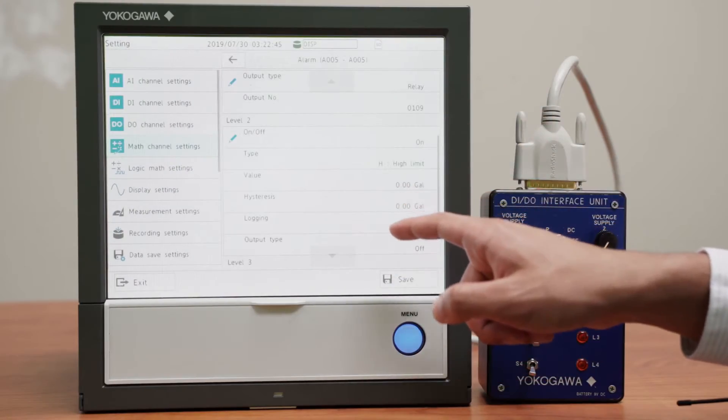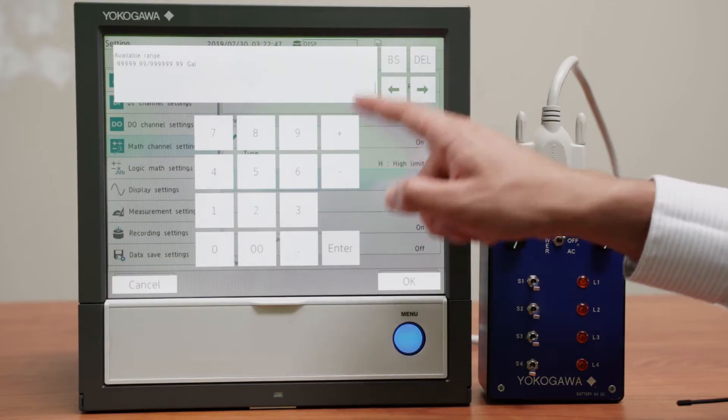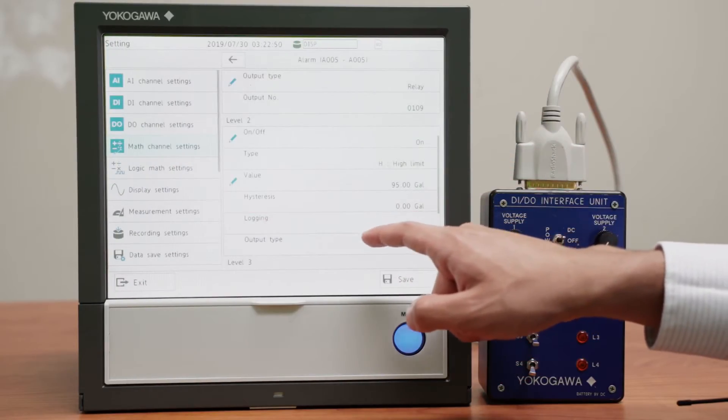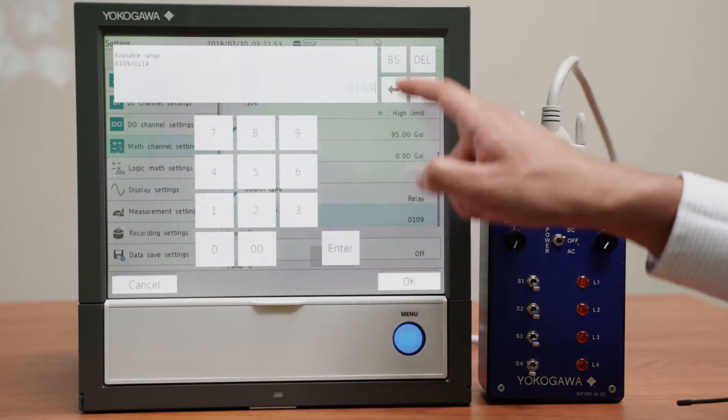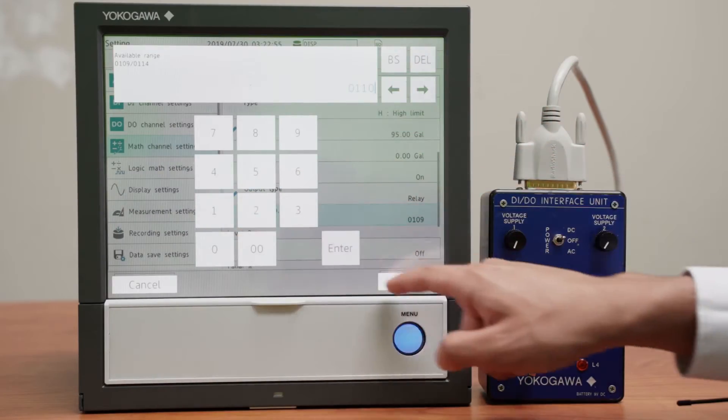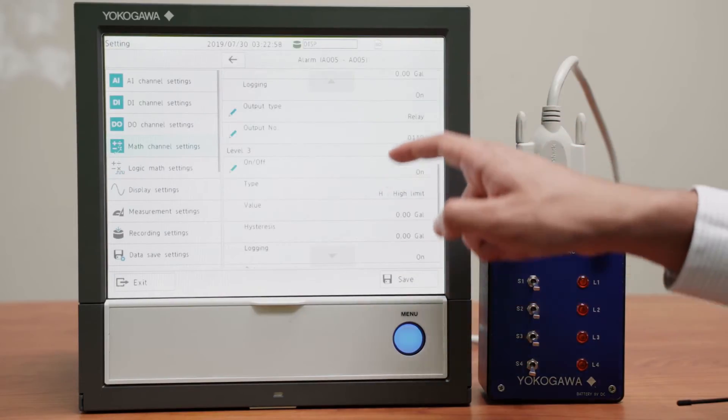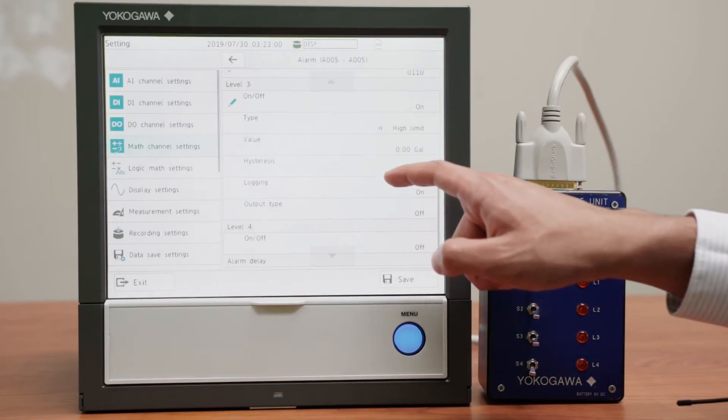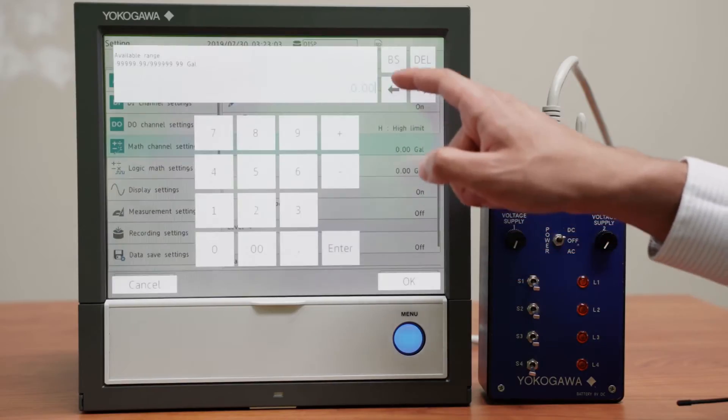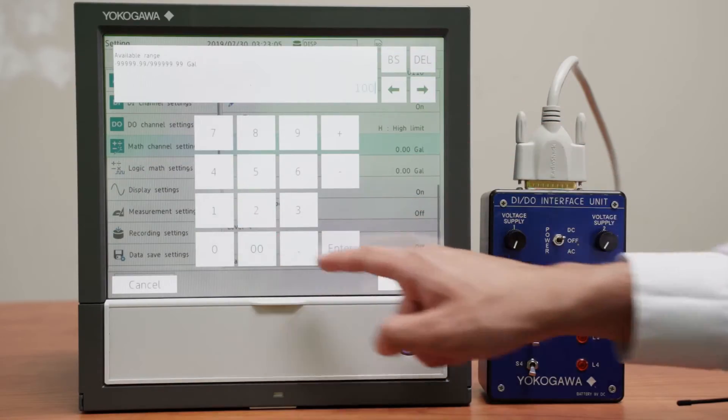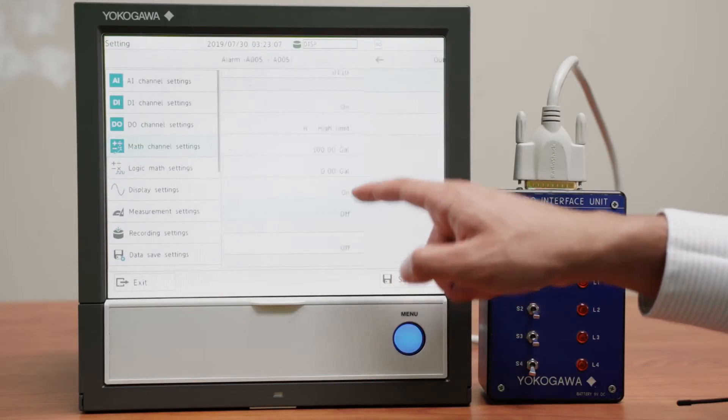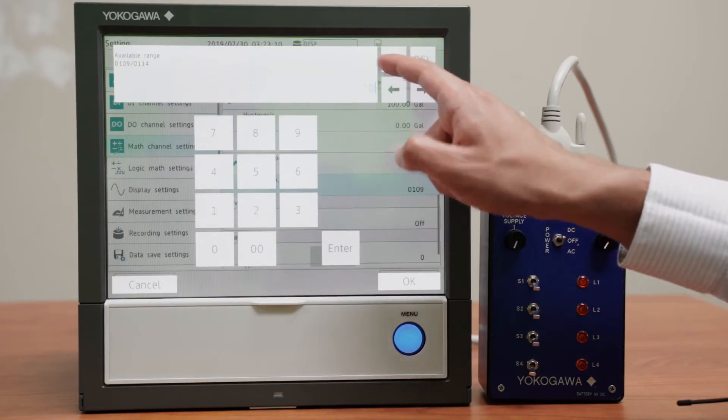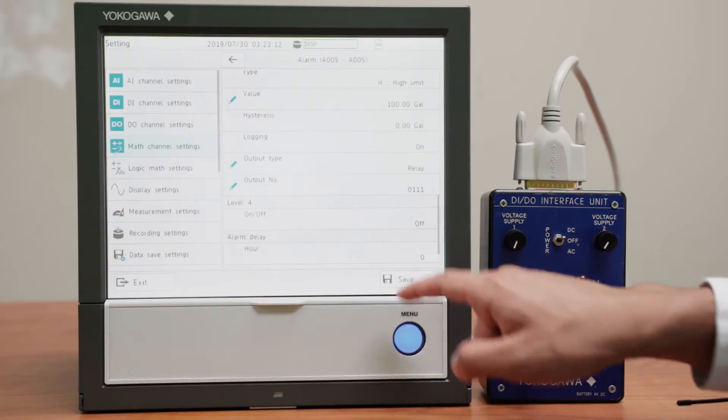Now I want the same but at 95, and I want the second relay to turn on, which is channel 110. For number 3, I want the same but at 100, and this will be our last relay alarm. That is channel 111.